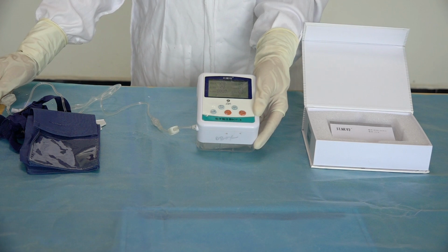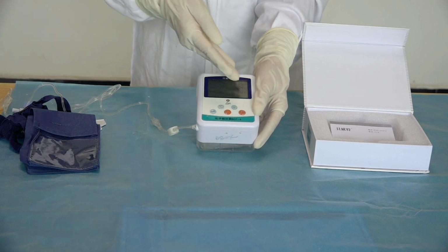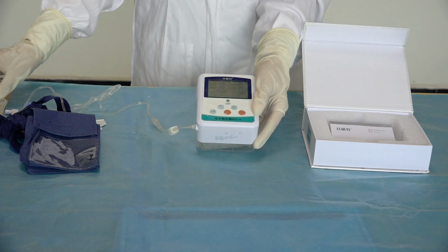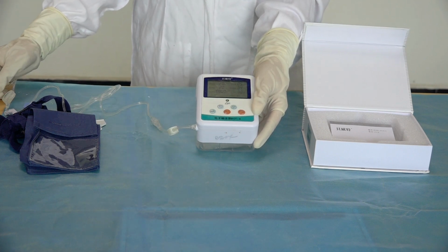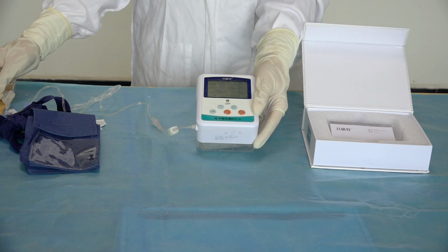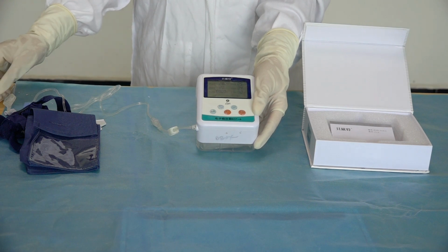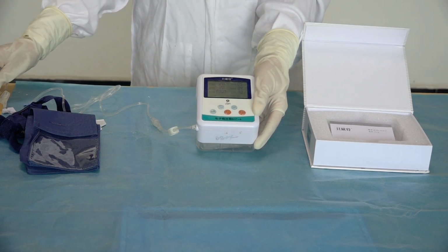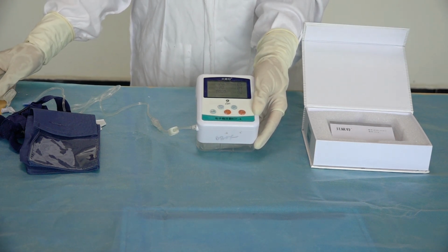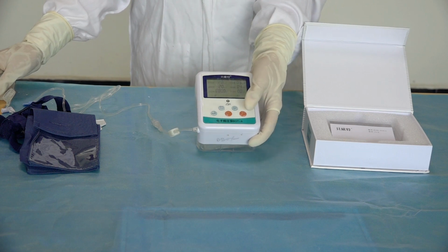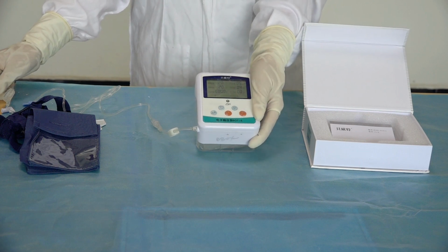Meanwhile, the word exhaust appears at the bottom right of the screen. The pump begins to exhaust air automatically, and then observe until no air bubble inside pipeline and medicine flows out normally. After the air exhaust is completed, and the word exhaust disappears on the screen, if you need to stop the exhaust when operating, only need to press the exhaust button again.